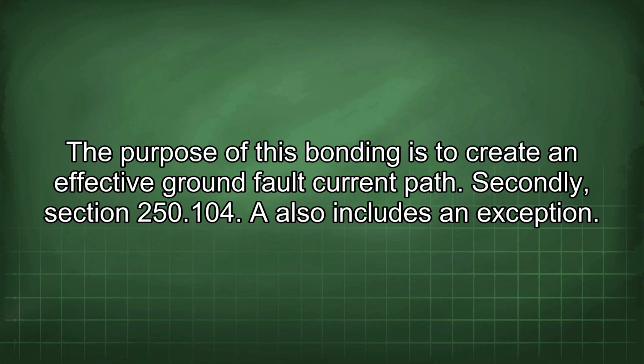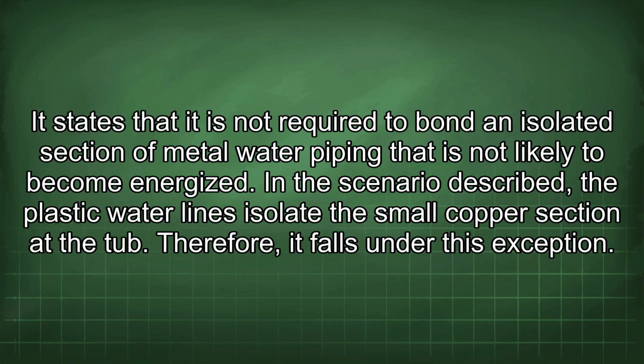Secondly, Section 250.104 also includes an exception. It states that it is not required to bond an isolated section of metal water piping that is not likely to become energized. In the scenario described, the plastic water lines isolate the small copper section at the tub. Therefore, it falls under this exception.